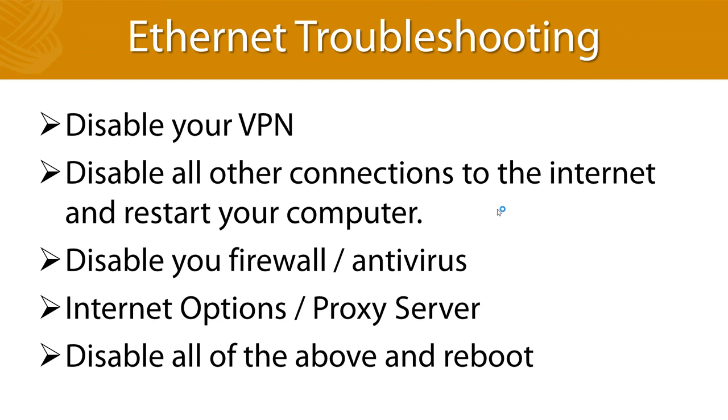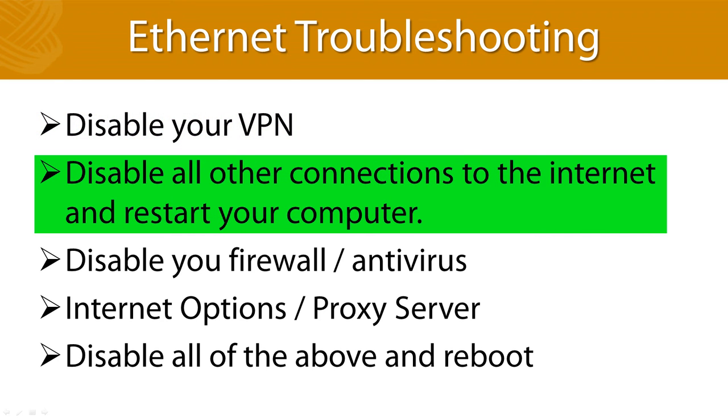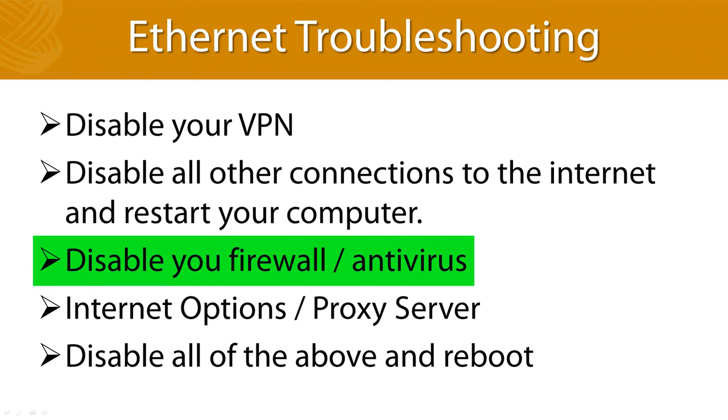If you set everything up properly and you still can't communicate, the first place to look for problems is with your corporate VPN. Make sure it is disabled because your VPN will try and shunt the information you want to go to the device through your office and that usually isn't going to work. If you were communicating for a while and it suddenly stops, that's usually a VPN kicking on and blocking communication. You theoretically should be able to communicate with the internet via Wi-Fi while simultaneously communicating with the device through another Ethernet port, but this configuration often causes problems. Sometimes your device Ethernet data tries to go through the Wi-Fi and vice versa. If you're still having problems and you know your VPN isn't the cause, try disabling all the other Ethernet communication except for the port that you need. Also remember that the Ethernet communication is the internet as far as your computer is concerned, so your antivirus and or firewall may be blocking communications as well. Make sure you are not connected to the internet first and then disable both to see if that helps.